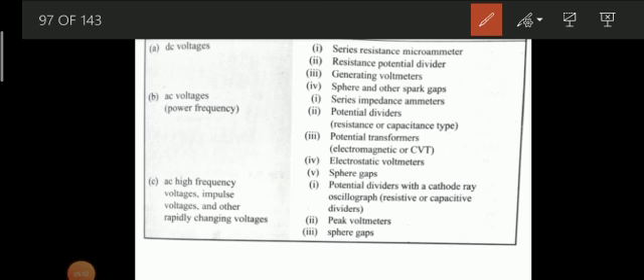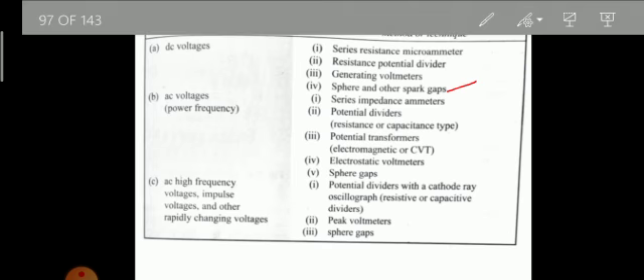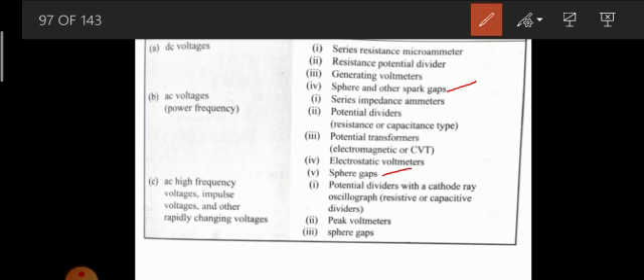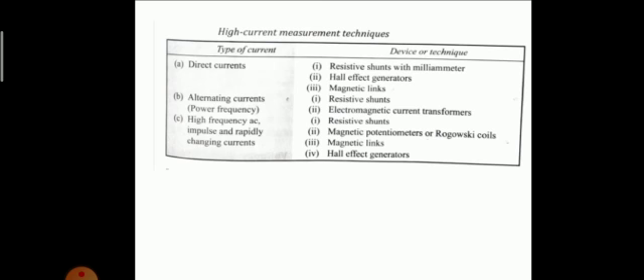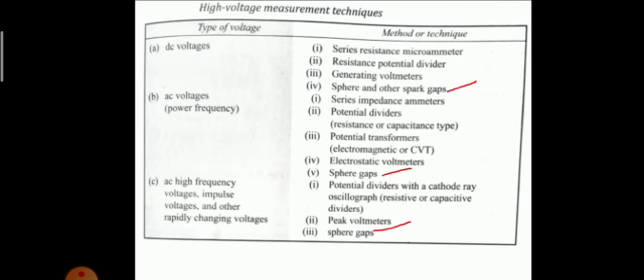Next we'll go for the sphere gap measurement. If I go back to the main slide where I had given you a table of various techniques, these are the measurement techniques. We use sphere gap measurement to measure DC voltages. We can use the sphere gap and spark gap to measure AC voltages, and also for measuring impulse voltages. Today we'll see the sphere gaps for measurement of DC voltages, AC voltages, high frequency AC voltages and impulse voltages.